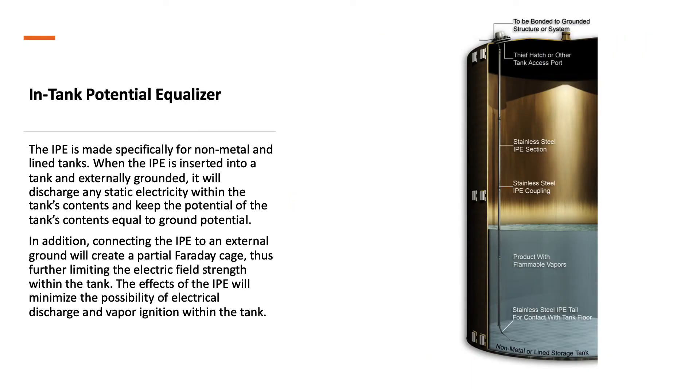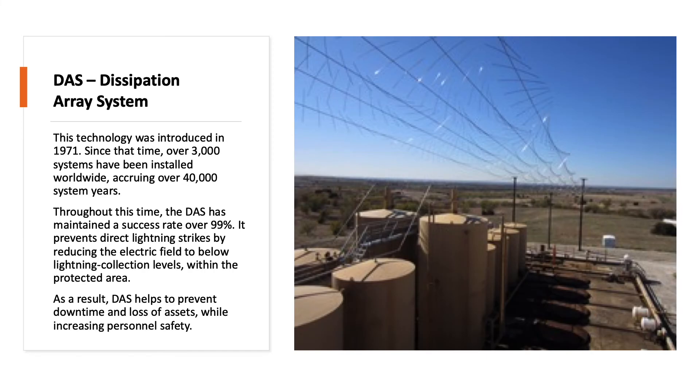The In-Tank Potential Equalizer, or IPE, is made specifically for non-metal and lined tanks. When the IPE is inserted into a tank and externally grounded, it will discharge any static electricity within the tank's contents and keep the potential of the tank's contents equal to ground potential. Connecting the IPE to an external ground also creates a partial Faraday cage, further limiting the electric field strength within the tank, minimizing the possibility of electrical discharge and vapor ignition.